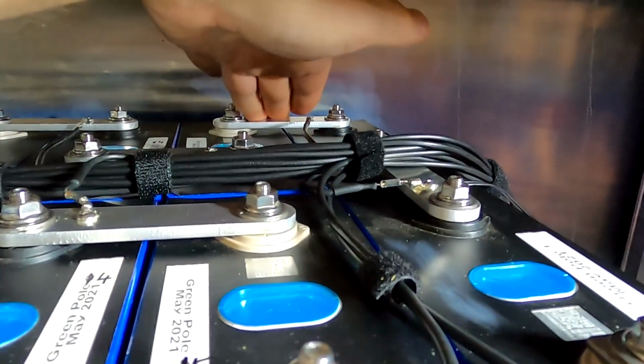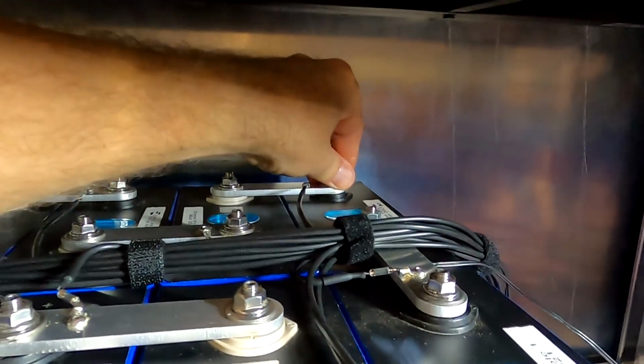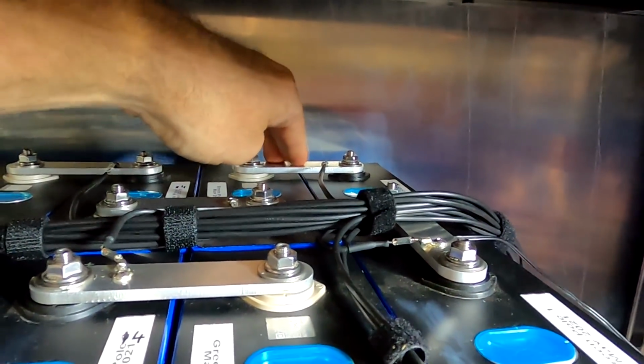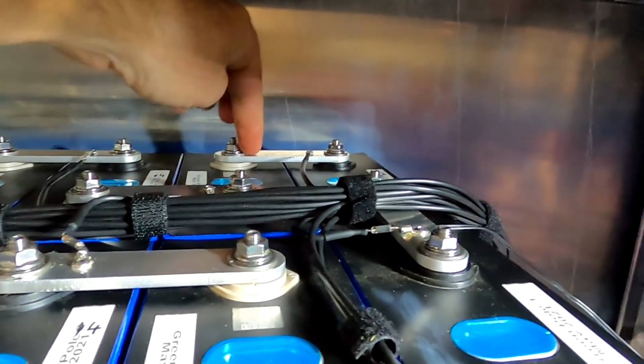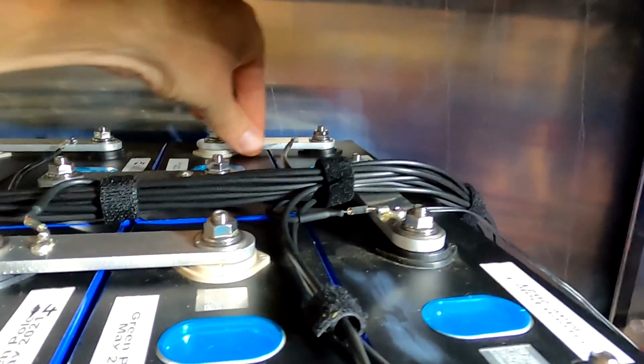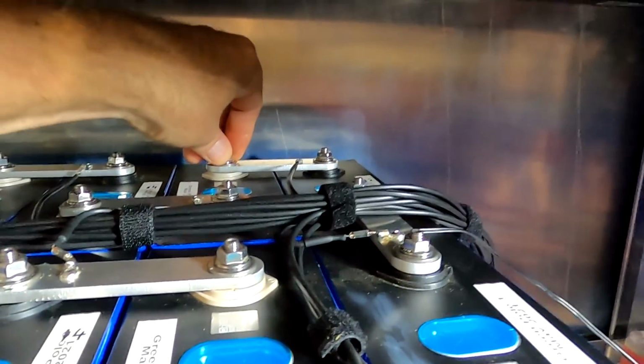See, this one is better now. It's still not super cold, but better than before. It was pretty hot, and I've just loosened the two nuts and wiggled the bus bar back and forward, then tightened them again with 5 Newton meters. Now it's a bit better, so it's definitely again a contact issue between bus bar and terminal.